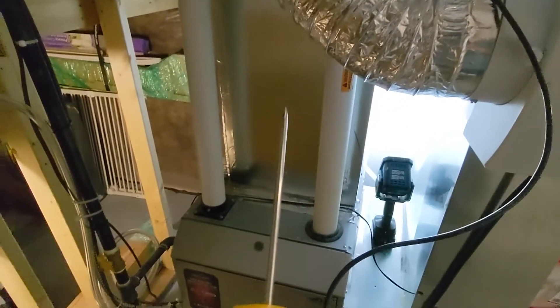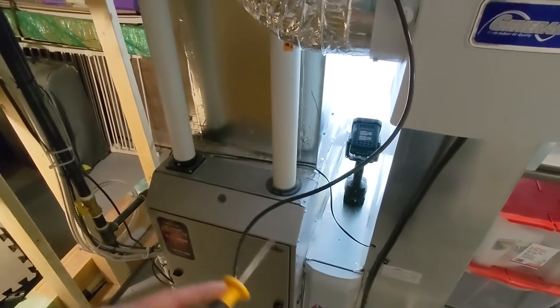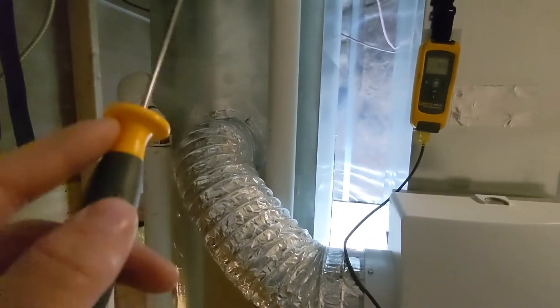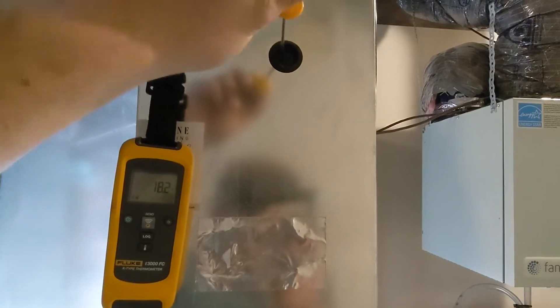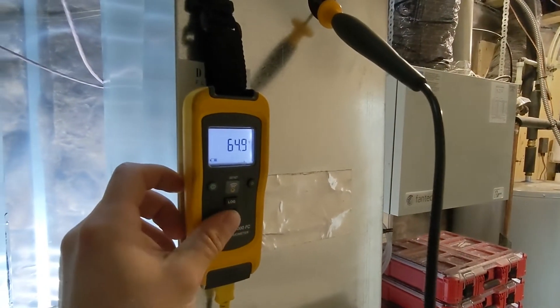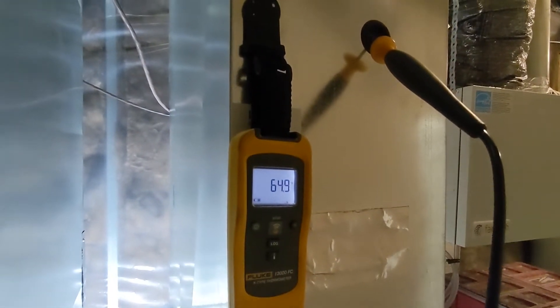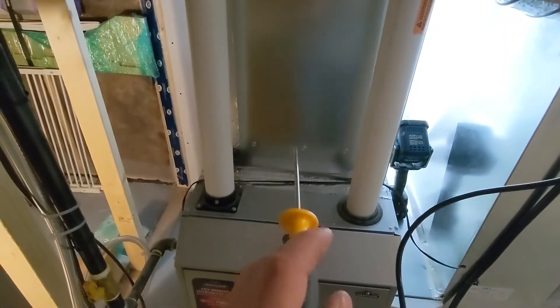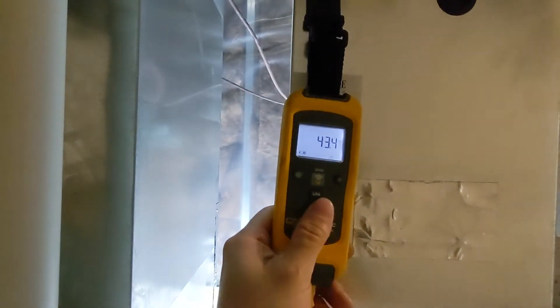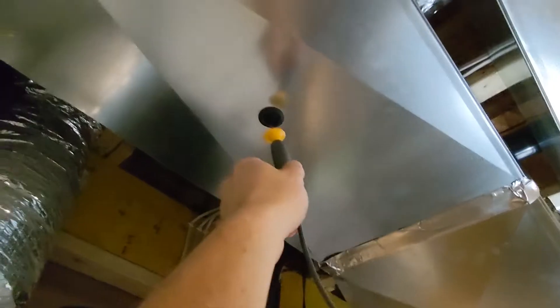Before we wrap this up, let's just go read some temperatures. I'm going to try to figure out the temperature difference across the coil — the coil lives right here. We'll read on the return side and then one on the supply side. On the return side we're getting about 18.2°C, 64°F — sounds about right, we should be getting around 65 to 75°F. Leaving the coil we got 43°F, 6.3°C — looking like about a 20-degree TD, which is healthy and what we wanted.